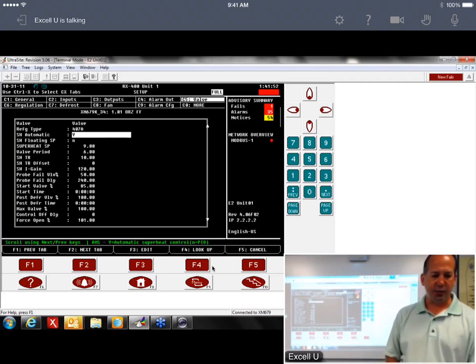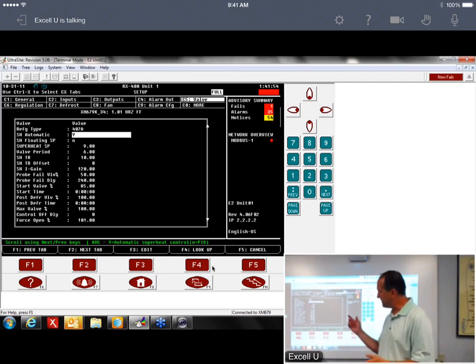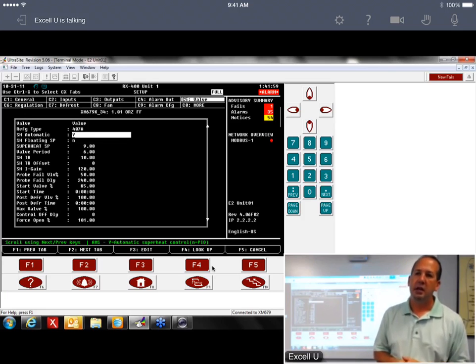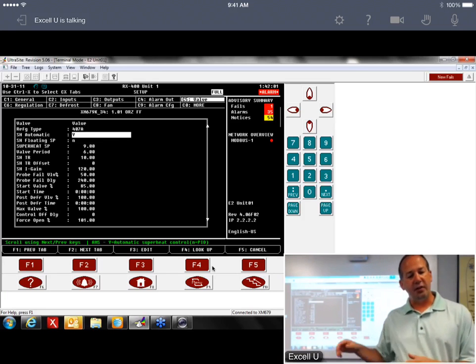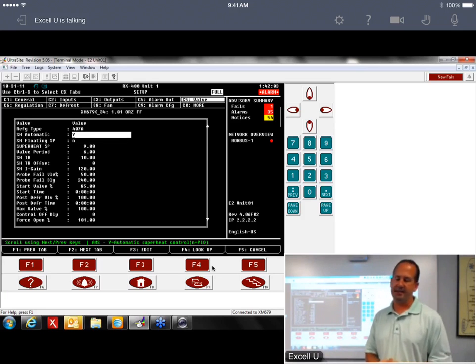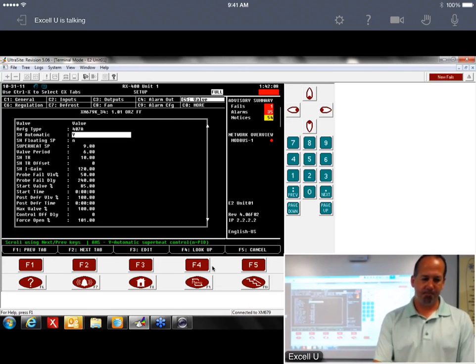And then this next one is Superheat Automatic. That's defaulted to yes. What that is, that enables the adaptive algorithm. You could turn that off, and then you could adjust all the PID settings. I wouldn't suggest it. I'd just leave it at yes.